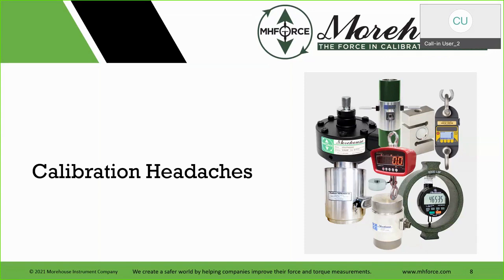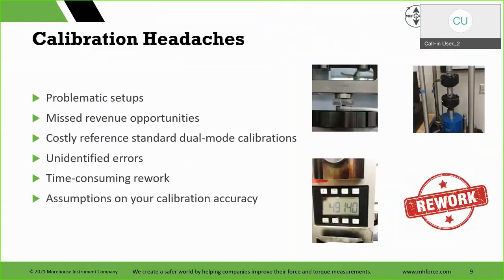So what we start looking at is, okay, we have this calibrating machine and we have these adapters. If we keep that line of force pure, free from the eccentric forces, we're going to do the right thing. So that's part of the headache: I have all these instruments, I want to set up a cal lab, and I have all these instruments that could come in, and how am I going to calibrate them? So that's where we have the adapters. So the headaches range from the setups, missed revenue opportunities. Maybe somebody has something that they want to send in and you don't have it. Costly reference standard dual mode calibrations. That's a picture over here. We'll talk about all of these.